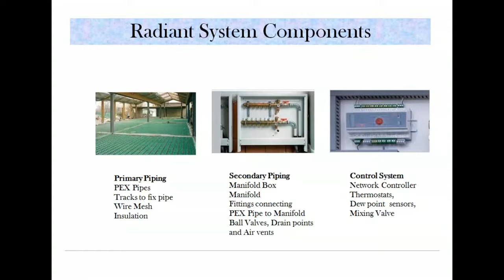Why? Because if you allow this surface to cool below the dew point temperature, then there will be condensation in this area. So to avoid that, we have a control system which keeps monitoring the dew point temperature in that area, and based on it, it decides what temperature water has to flow into the radiant system. That is the reason we call it the heart of the system. Otherwise, all the other features are very easy to install and maintain.